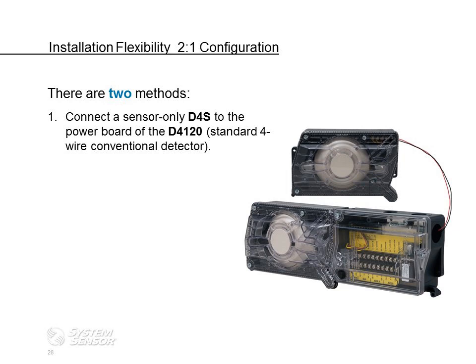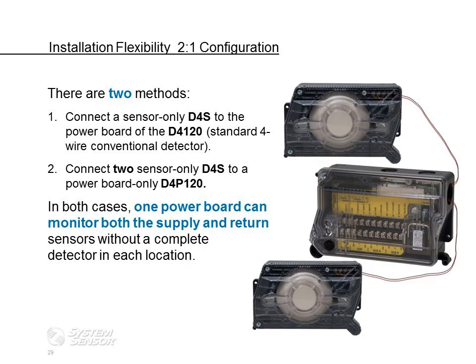One way to do it is to connect the sensor-only D4S to a standard 4120 on the power board. So you would have one standard duct detector and then one detector-only D4S, connect them together to cover the supply and return. The second way that you can meet this requirement is by connecting two sensor-only D4Ss to a power board only, which is a D4P120.